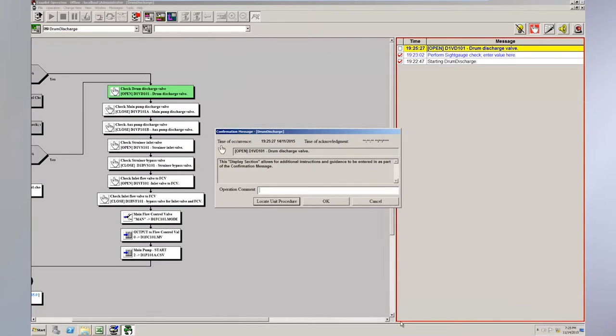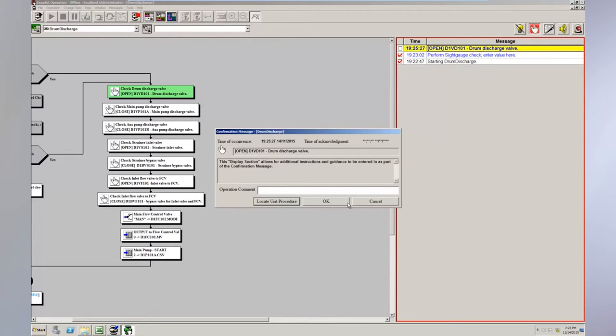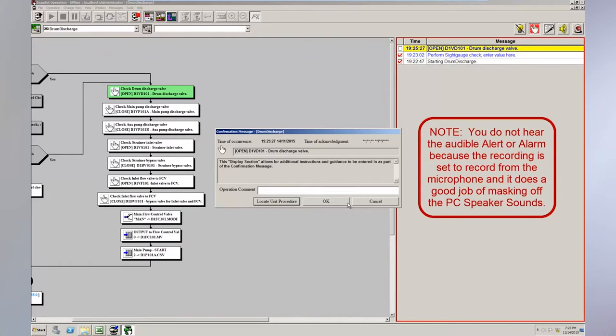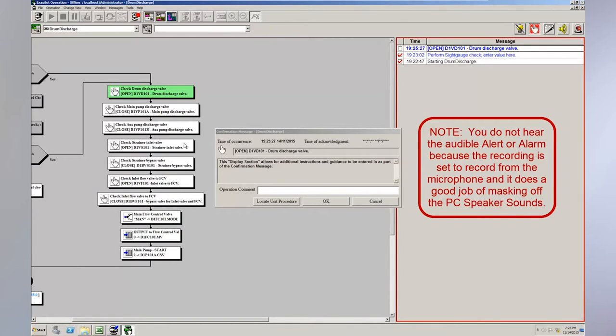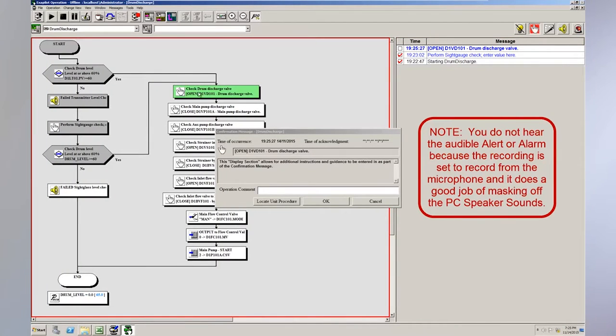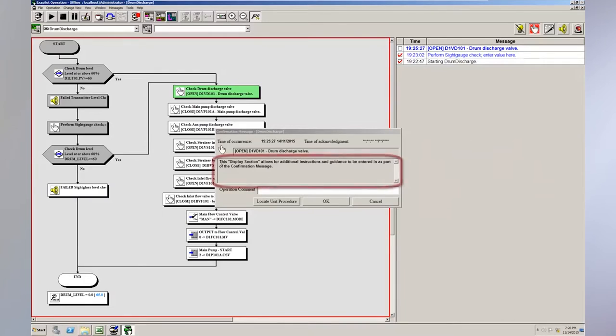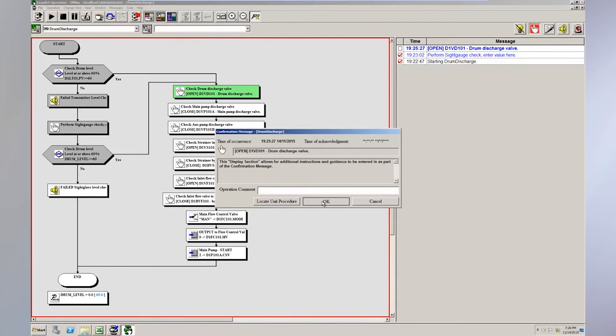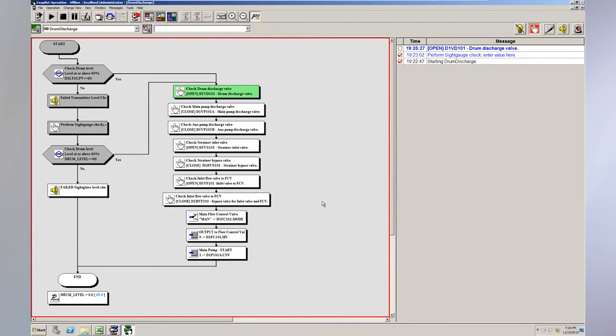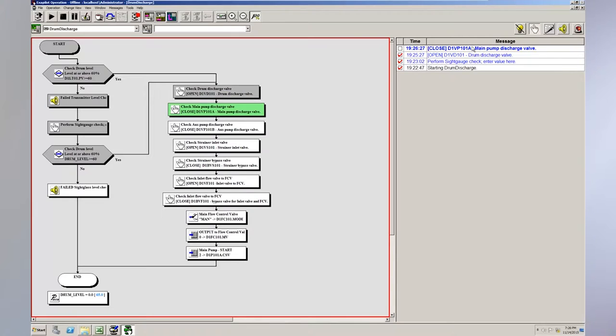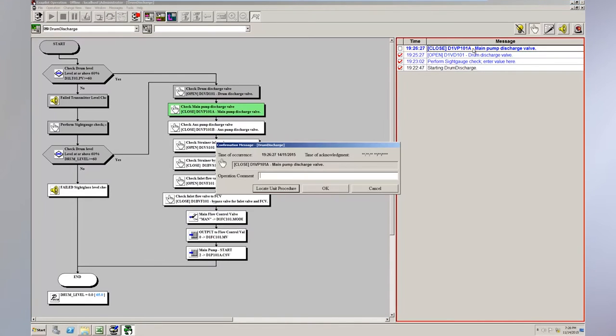Since we're not integrated with a DCS, it's just nicer to see us go along. So now we see that we did pass the test and we're being prompted to open the discharge valve. And you can still hear a tone. And this tone sounds, I'm going to silence it here with the silence button. That tone sound is because you may recall when I was developing the application for this very first valve lineup check, we left the tone on. And that gives you an audible as well as this visual pop up letting the operator know he needs to perform an action. So I'll say, and also I'll note here, I'll point out here, I get this extra verbiage that I typed in. It says, this display section allows for additional instructions. Because I selected the little check box there for additional text space. These remaining sections don't give me the, if I select it, don't give me an audible. If I select this, I don't get the extra set of instructions there. It just gives me the brief prompt that we typed in, close the main discharge valve.